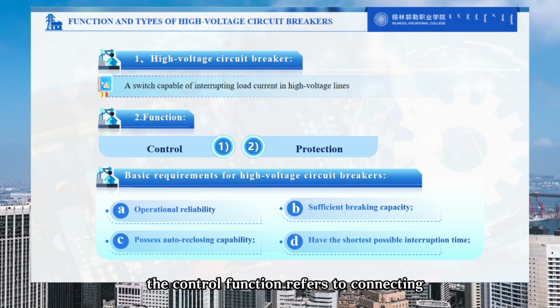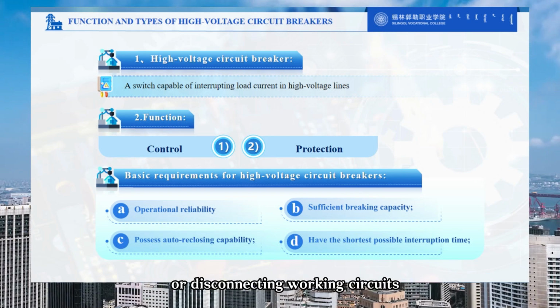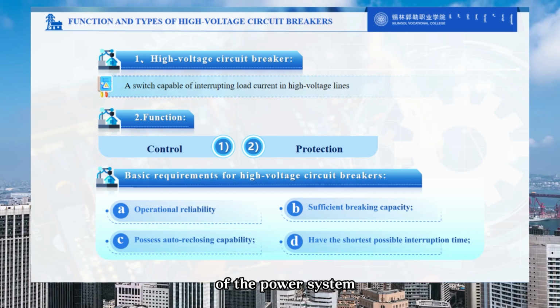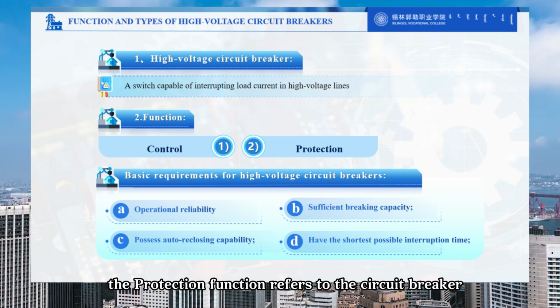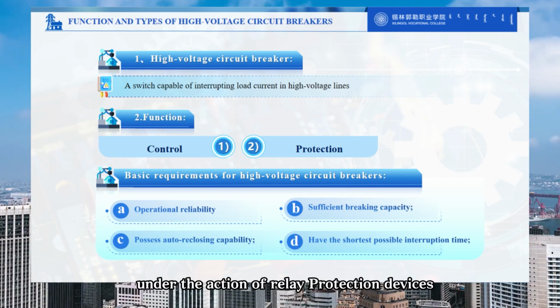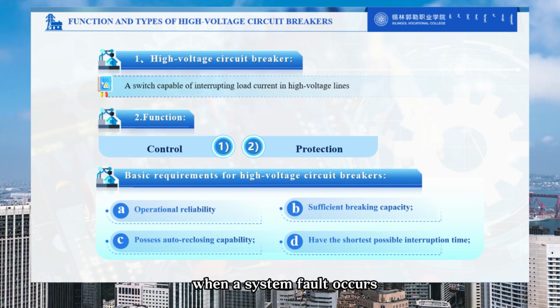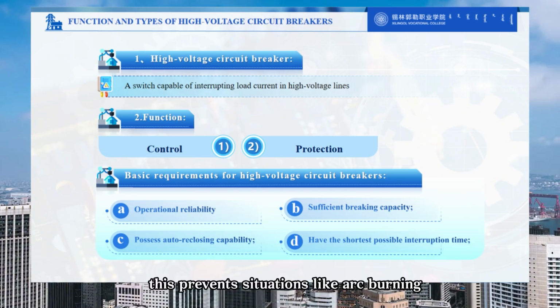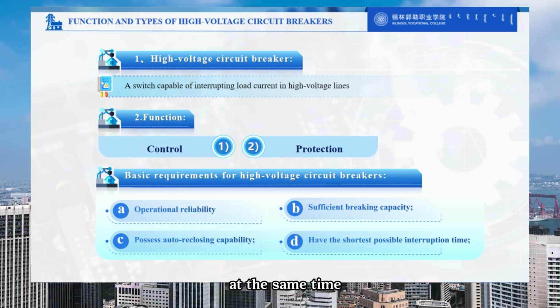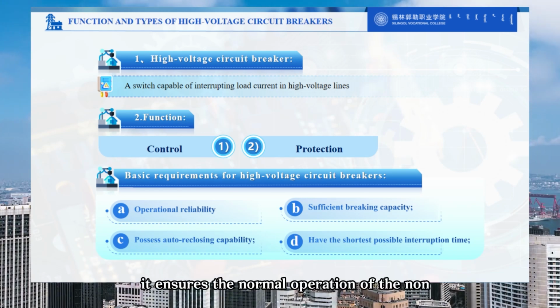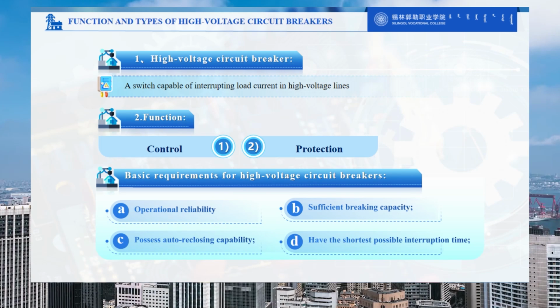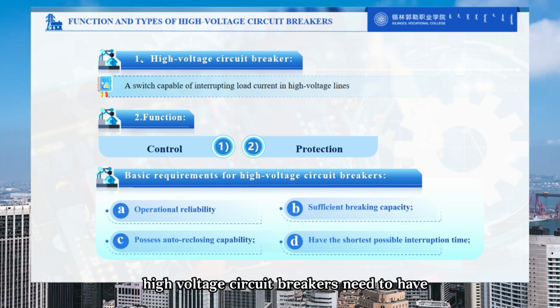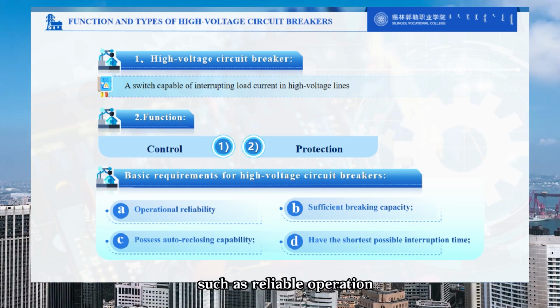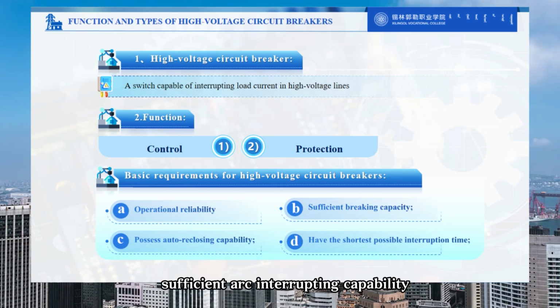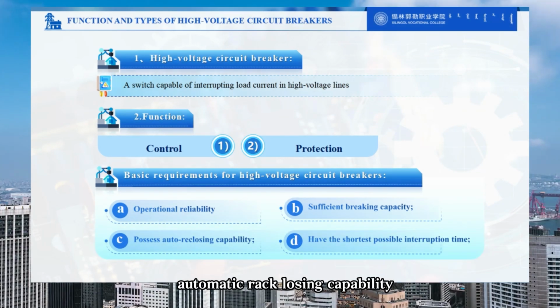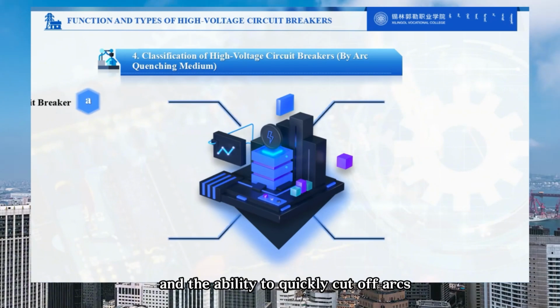The control function refers to connecting or disconnecting working circuits based on the operational requirements of the power system. The protection function refers to the circuit breaker quickly isolating the faulty part under the action of relay protection devices when a system fault occurs. This prevents situations like arc burning. At the same time, it ensures the normal operation of the non-faulty parts of the system. In practical production, high-voltage circuit breakers need to have characteristics such as reliable operation, sufficient arc interrupting capability, automatic reclosing capability, and the ability to quickly cut off arcs.